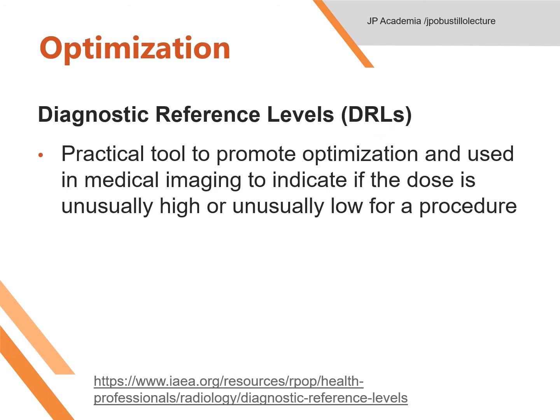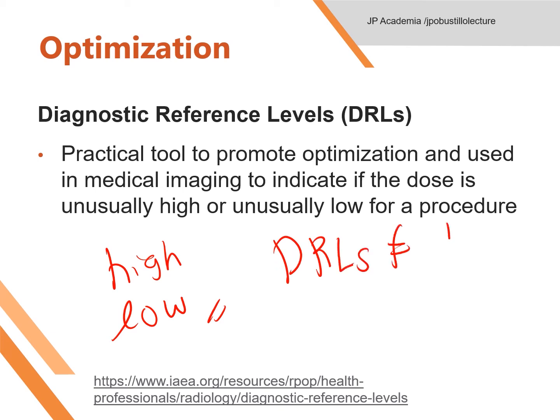Still under optimization, we have Diagnostic Reference Levels or DRLs. This is a level used in medical imaging to indicate whether, in routine conditions, the dose to the patient or the amount of radiopharmaceutical administered in a specified radiological procedure is unusually high or unusually low for that specific procedure. DRLs are a practical tool to promote optimization, first successfully implemented in relation to conventional radiography in the 1980s. It is important to recognize that DRLs are one step in the overall process of optimization — they are not applied directly to individual patients, but a local review may be done based on established DRLs. Note that DRLs are not the same as dose limits.